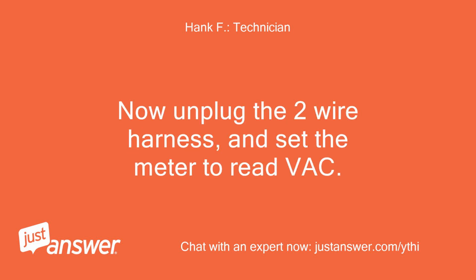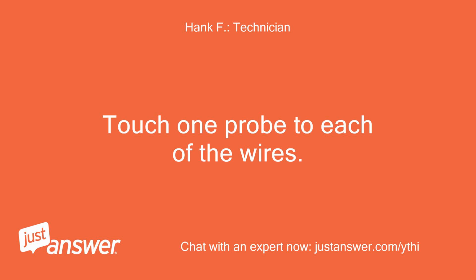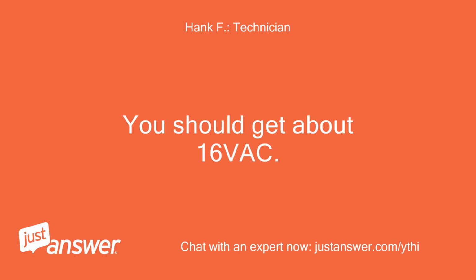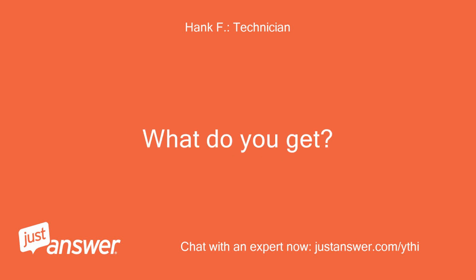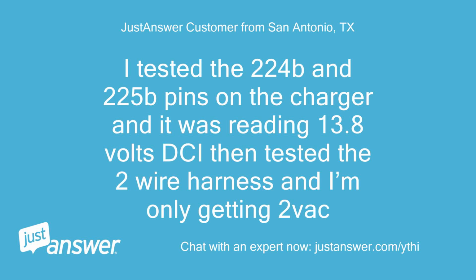Now unplug the 2-wire harness, and set the meter to read VAC. Touch one probe to each of the wires. You should get about 16 VAC. What do you get? I tested the 224B and 225B pins on the charger and it was reading 13.8 volts DC. I then tested the 2-wire harness and I'm only getting 2 VAC.